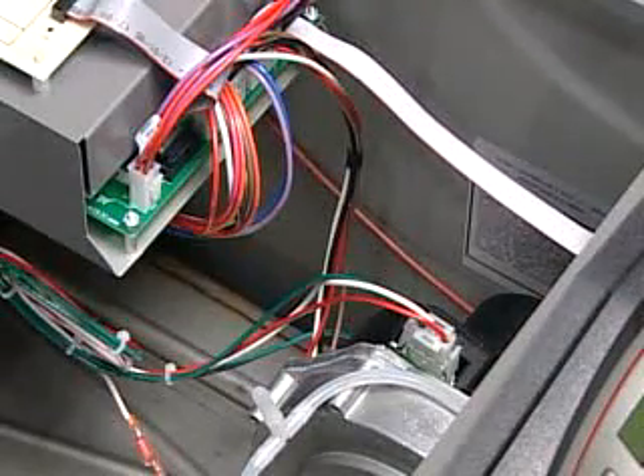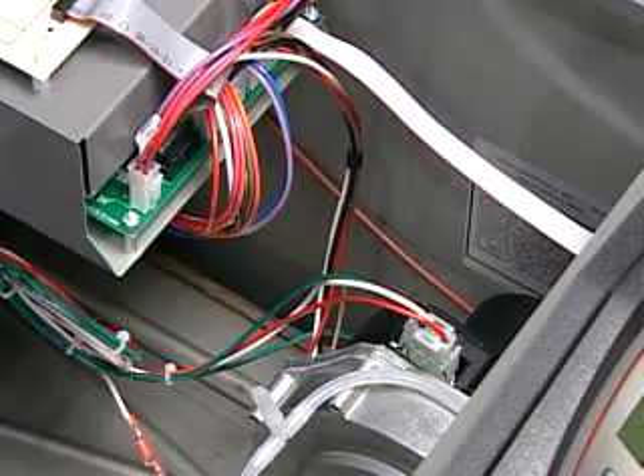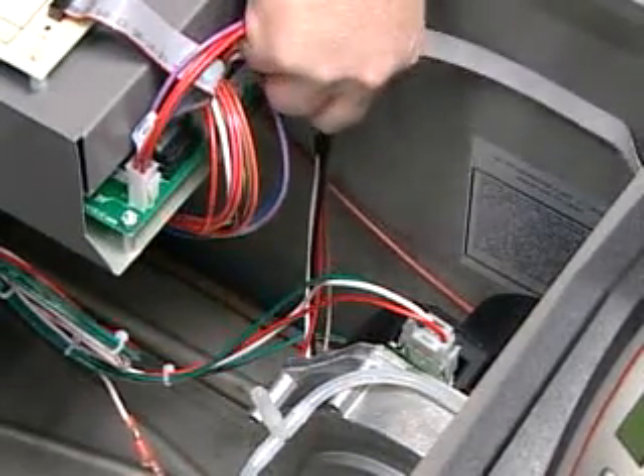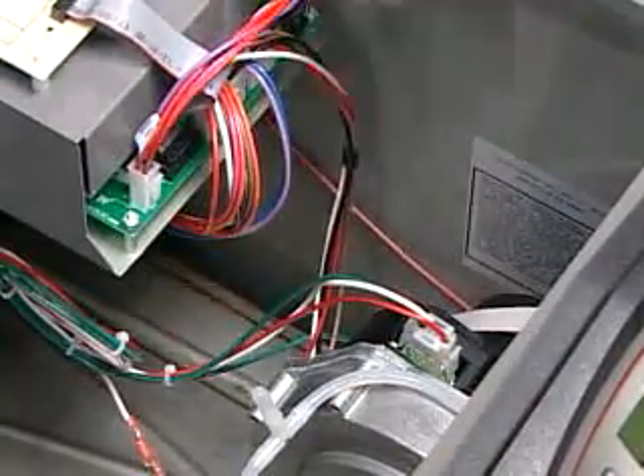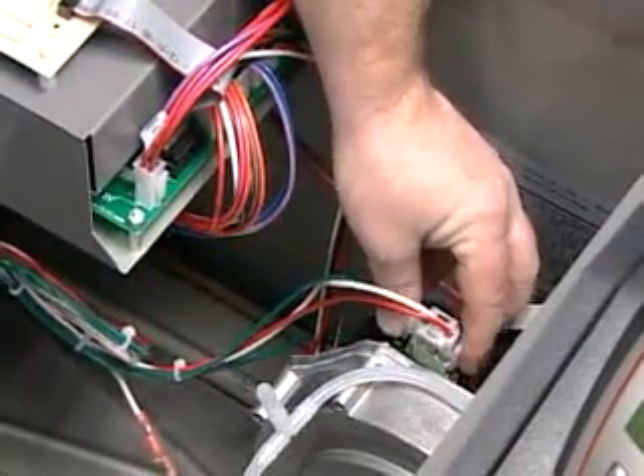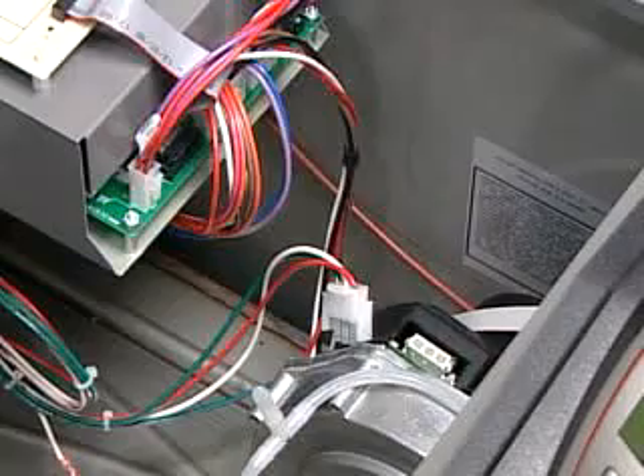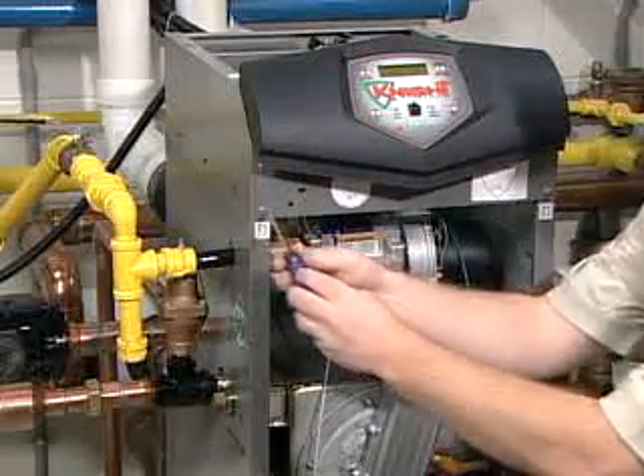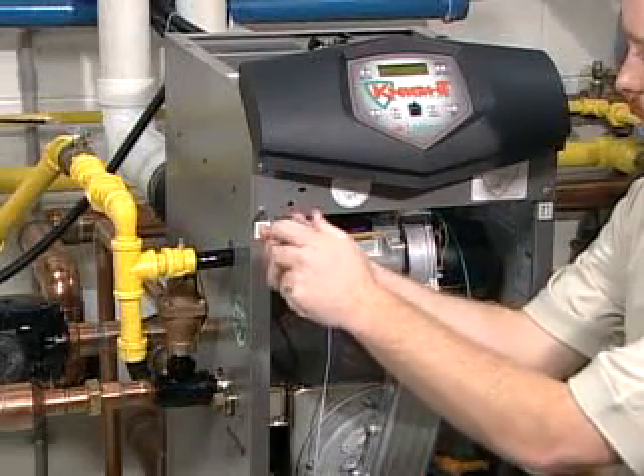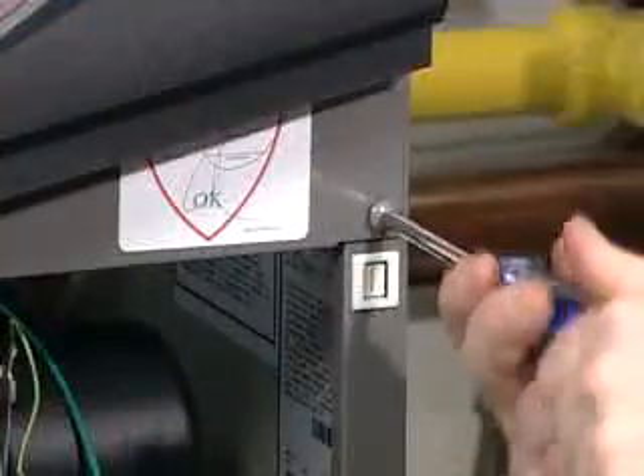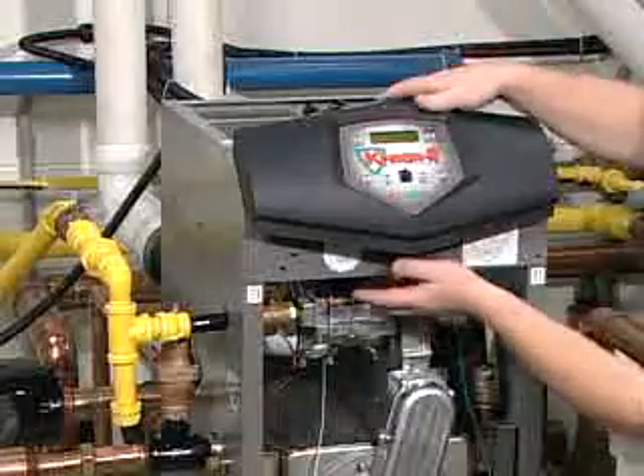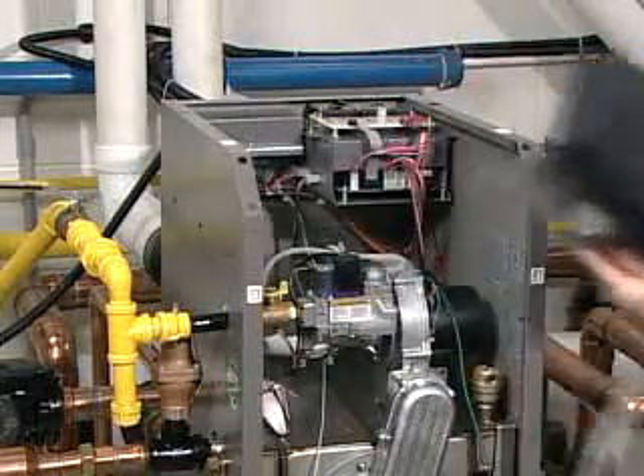Locate the ribbon cable from the display board to the main control board. Remove the cable from the main control board. Locate and disconnect the two wiring harness connections on the combustion blower. Using a Phillips screwdriver, remove the 6 screws securing the bezel to the unit. Remove the bezel from the front of the unit.